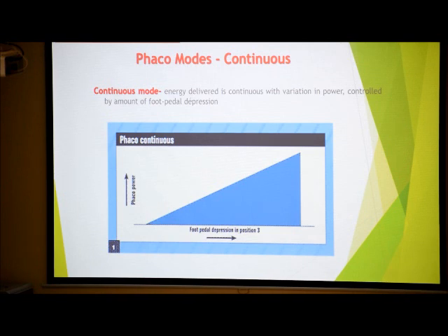Delivery of phaco power into the eye can be in different modes. The most common and basic one is continuous mode, where energy is delivered continuously without any break, controlled by the amount of foot pedal depression. As the foot pedal depression position increases, phaco power increases, as the graph shows.